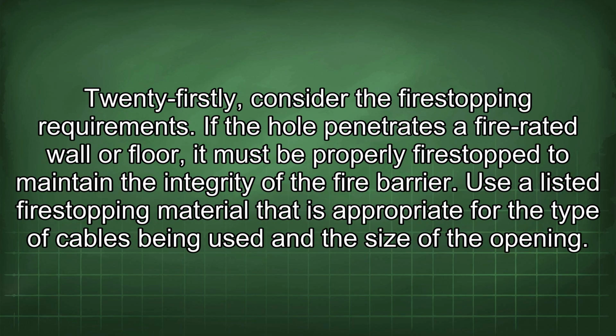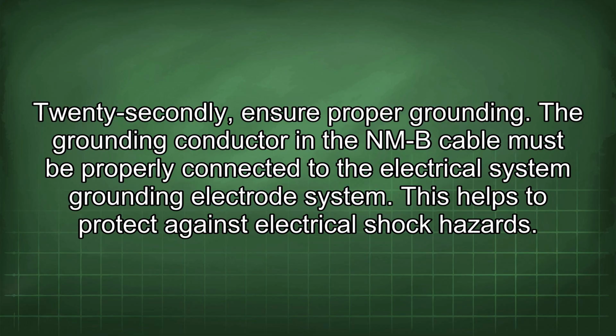21stly, consider the fire stopping requirements. If the hole penetrates a fire-rated wall or floor, it must be properly fire-stopped to maintain the integrity of the fire barrier. Use a listed fire-stopping material that is appropriate for the type of cables being used and the size of the opening. 22ndly, ensure proper grounding.